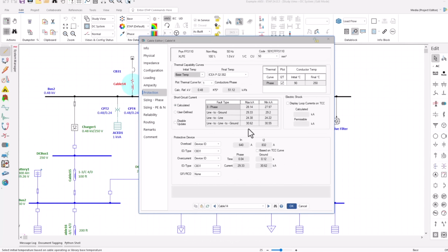The fault clearing time is updated based on the overcurrent protective device selection. In this case, I have selected CB31 to serve as the protective device for this cable. Based on the clearing current characteristics of this breaker, the combination of the fault current and time, which produce the highest energy I²T, is automatically determined. The fault current and clearing time are also displayed. These values are then used for sizing the phase conductor.